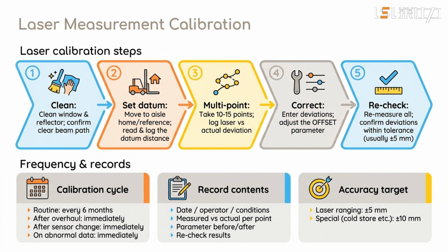Now the laser calibration, in 5 steps. Step 1. Clean. Wipe the window and reflector and ensure the beam path is clear. Step 2. Set the datum, drive the stacker to the aisle home position, and log the current laser reading. Step 3. Multi-point measurement. Take 10 to 15 points along the aisle, and record the deviation between laser and actual at each. Step 4. Correct. Enter the deviations into the controller and adjust the offset parameter. Step 5. Recheck. Remeasure from the start and confirm every point is within tolerance. Calibrate every 6 months as a rule, and immediately after changing a sensor.